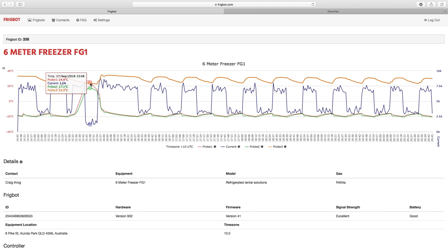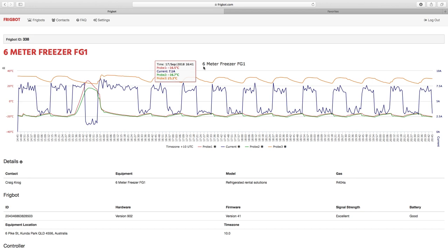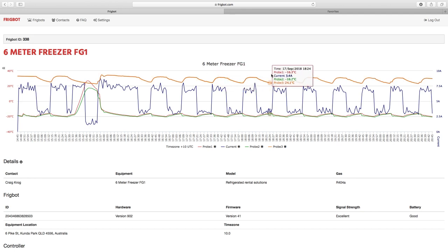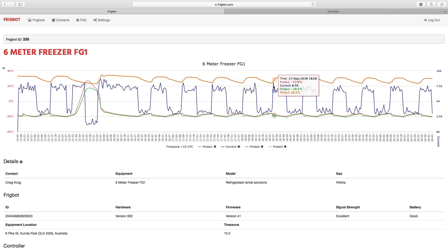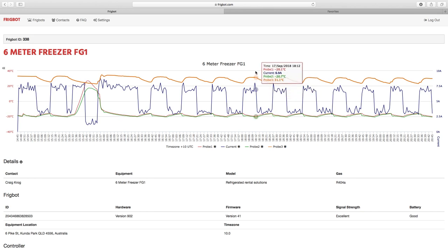So in this case this is a 6 meter long freezer, it's 2.5 meters wide, it's 2.5 meters tall, and generally speaking through the day it seldom goes above 7.5 amps.